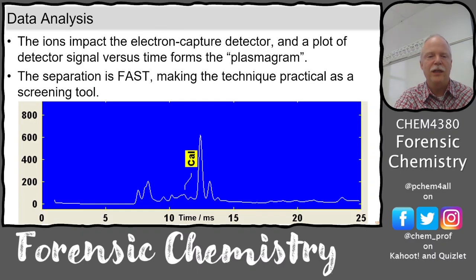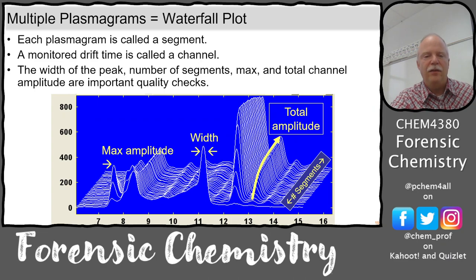So here's the calibration gas, that dichloromethane. It drifts down the tube and hits the detector. When you have another substance in it, notice how the calibration gas signal disappears. This first trace in the plasmagram waterfall plot is the calibration gas, and then the other substance grows in, stealing all the electrons from the calibration gas, and it's now ionized and detected.